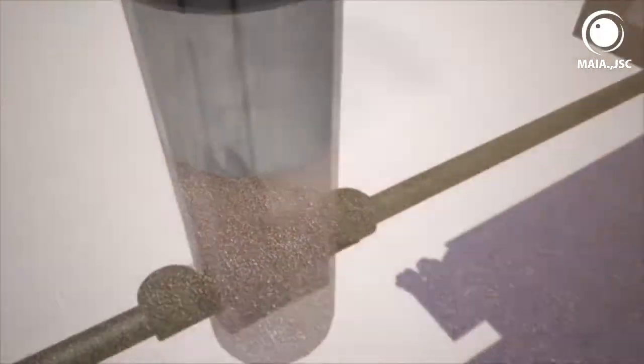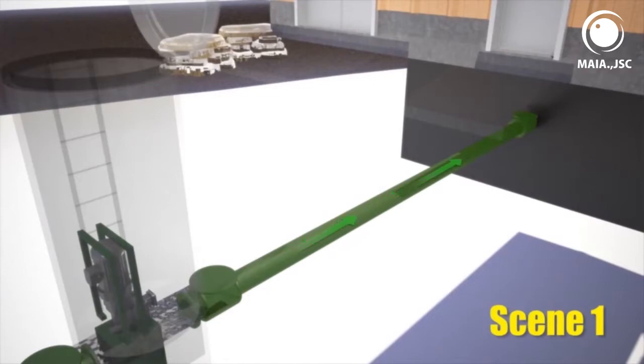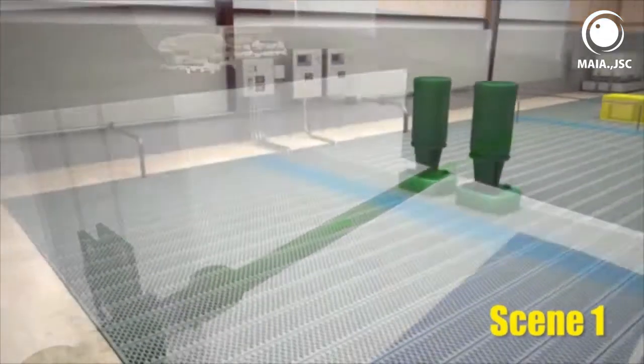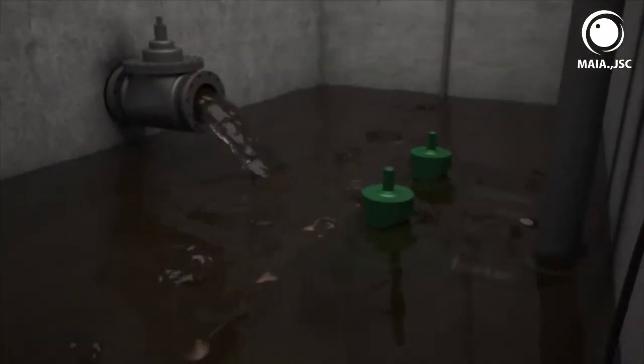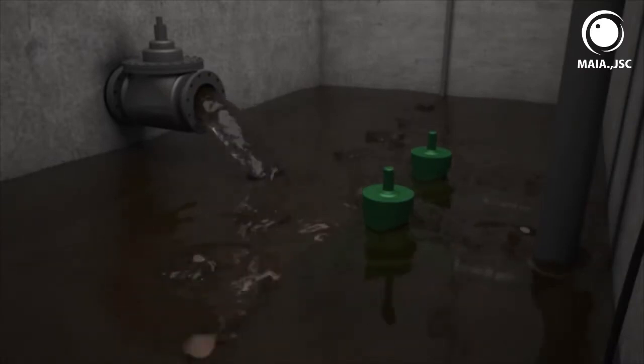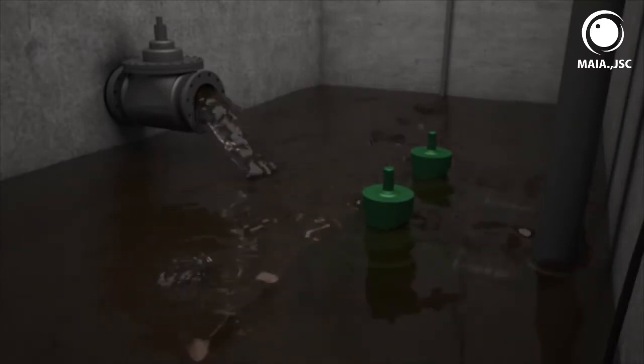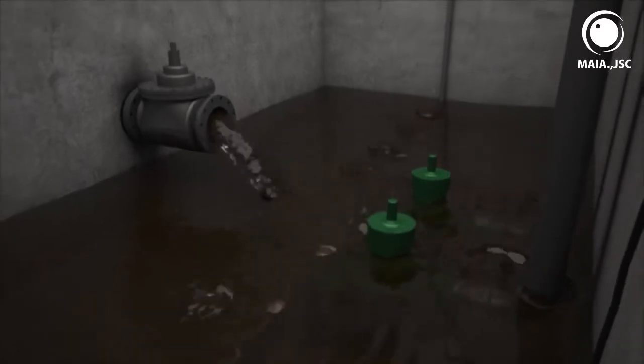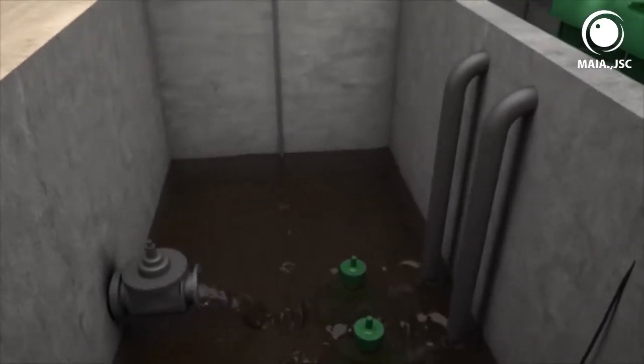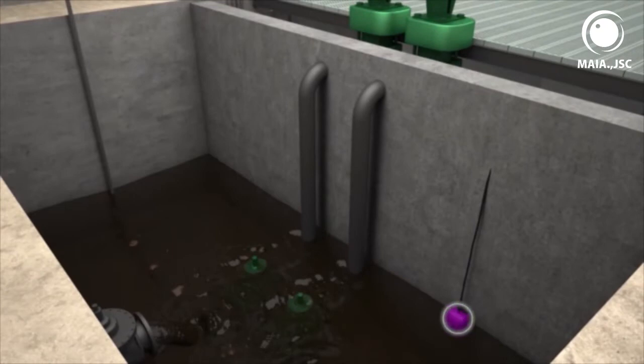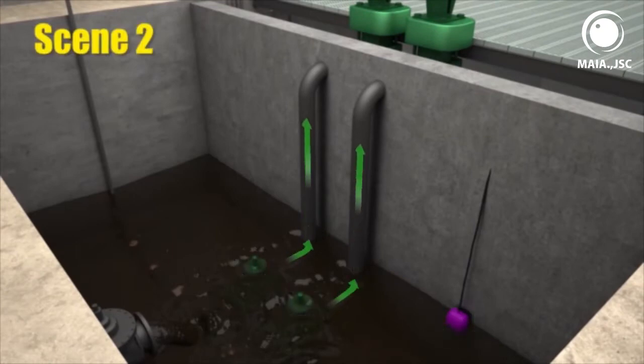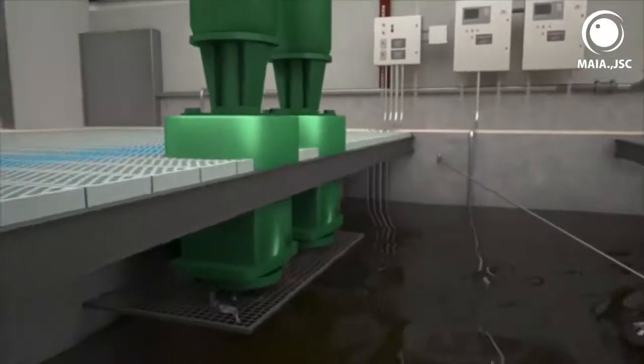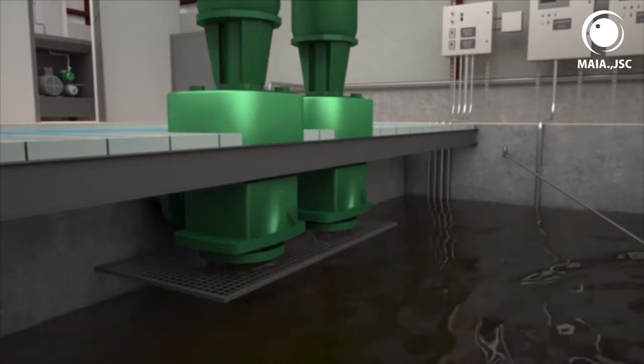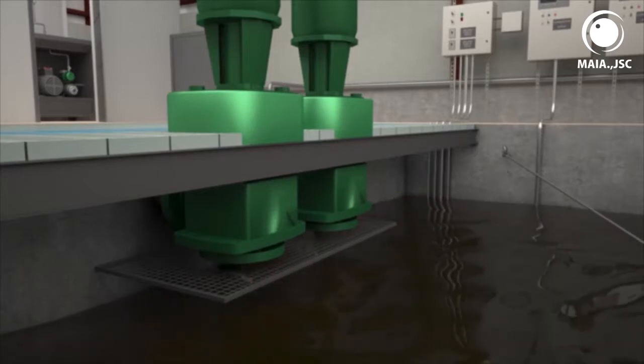The mechanically shredded wastewater then flows by gravity to the influent lift flow equalization chamber inside the building. This tank is designed to balance the varying flows of water activity throughout the day. Once the wastewater reaches a certain level, a float switch activates one of 2 cycling pumps and transfers a portion of it into the aeration chamber. During the transfer process, it also passes through a second comminutor to further break down any remaining solid materials.